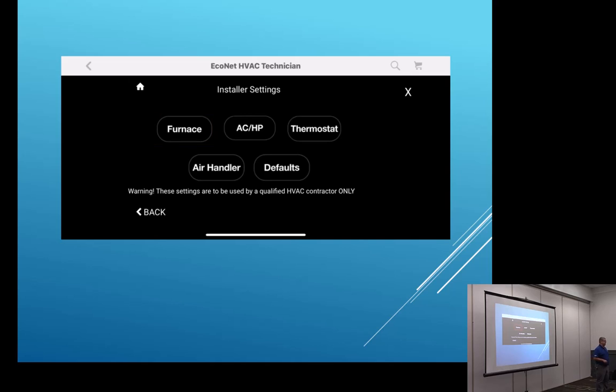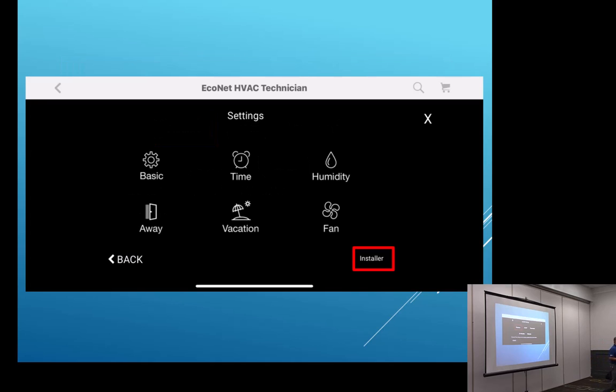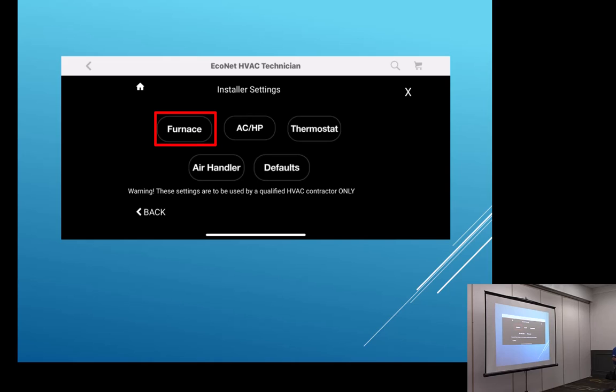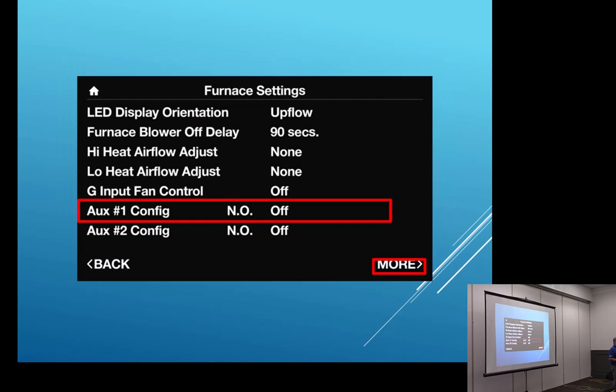Installer. To get into the installer menu, you have to hold the installer button down for 5 seconds. It can bring you into here. They have taken the history of alarms, which this doesn't show, and the history of alarms are now in the installer section because it was out in the open menu and homeowners would go through there and clear the alarms trying to get the unit back running, and then you get out there and don't know what alarms is in it. Or you're still going to find the smart ones that figured out how to get into the installer and they'll still do it. But it's better this way, at least. We kind of hid it a little bit. So you're going to want to look at the current alarms and the history of alarms.